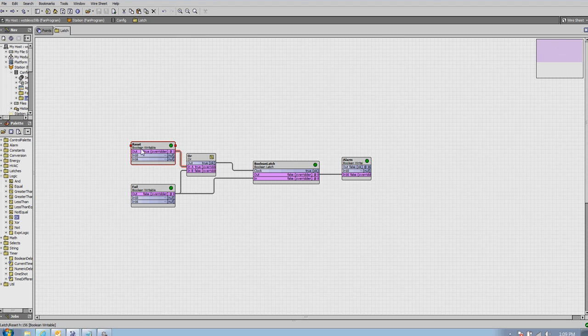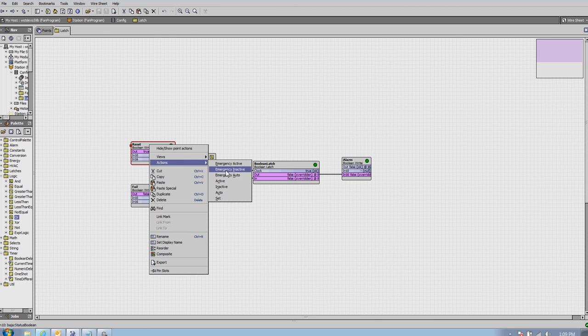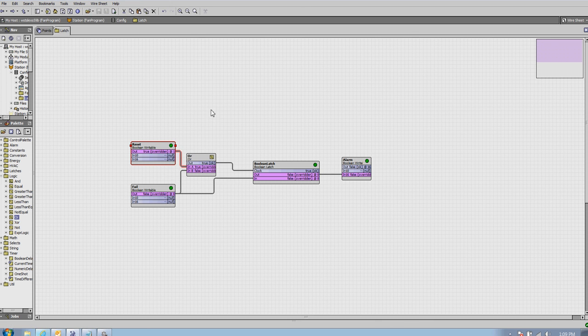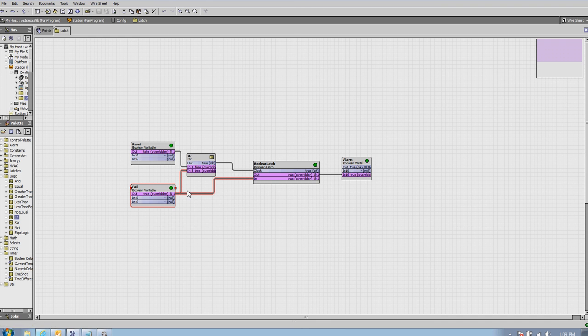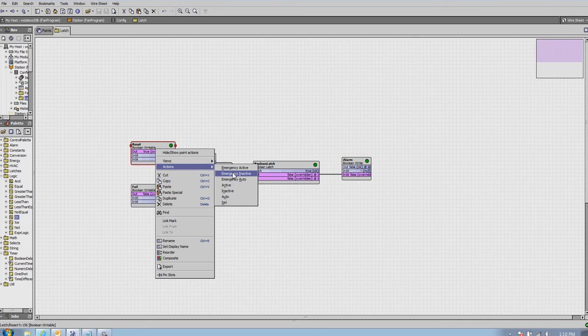Your reset point should always be in a false state until you go to use it. And I'll show you how to set that up in a graphic here momentarily. But typically, this is just a momentary execution. When you change this from false to true, it's only a momentary state. So now if I go back to active, it's going to toggle it to true. The fault clears. Even though my input says that my fail has gone to the false state, my alarm is latched in until the user comes here and resets it. So right there is what we want.